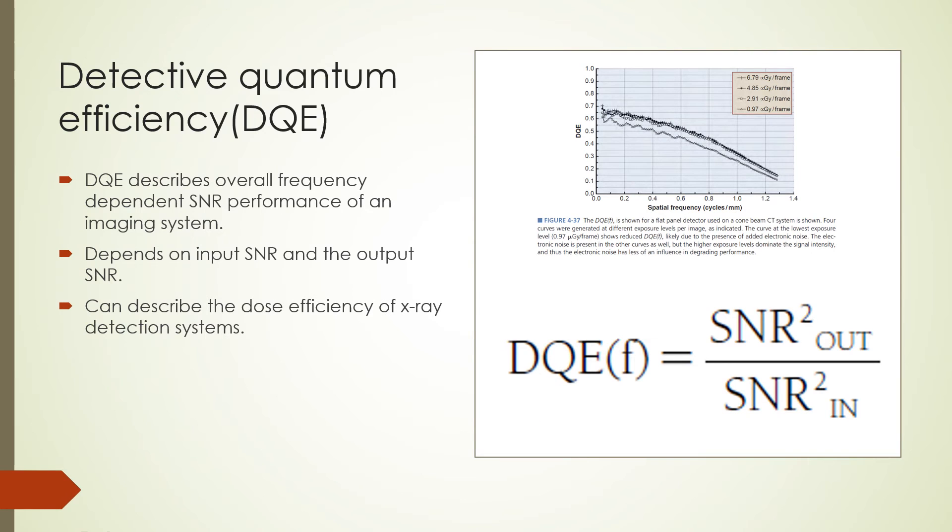We have here a quantitative method for analyzing spatial and contrast resolution by using the detective quantum efficiency. The detective quantum efficiency is a characterization used by imaging scientists. It describes the overall frequency-dependent signal-to-noise ratio performance of the imaging system. It uses the input signal-to-noise ratio and the output signal-to-noise ratio to calculate the detective quantum efficiency as shown by the formula on this slide. It is considered an excellent description of the dose efficiency of an X-ray detection system.